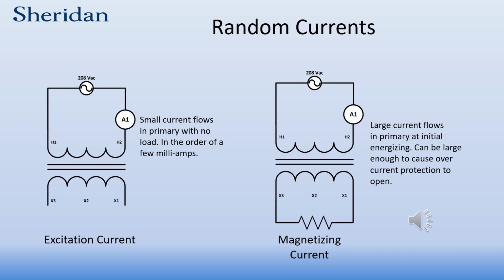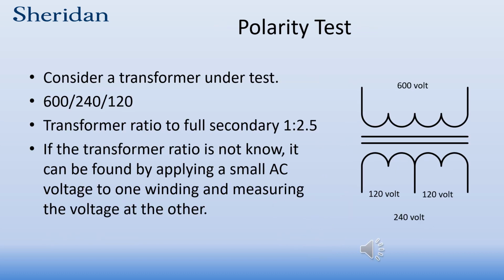If you energize the transformer at the peak of the AC cycle, magnetizing current is going to be greater, and if you energize it at the zero of the AC cycle, the magnetizing current will be less. Next is a polarity test. In some cases, it is really essential to know the polarity of the transformer. Keep in mind that transformers don't have negative or positive, they're AC. What it does is it determines what terminals on the transformer are at the same polarity at the same instant of time. So let's look at this transformer.